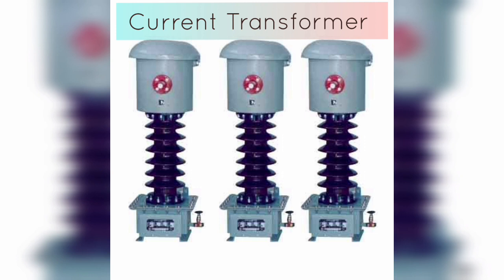An electrical current transformer (CT) is a type of instrument transformer used to measure high levels of electrical current in power systems. CTs work on the principle of electromagnetic induction, where a changing magnetic field induces a voltage in a conductor. The primary winding of a CT is connected in series with the conductor carrying the high current to be measured. The secondary winding is connected to a measuring instrument such as a meter or relay, and provides a reduced current output proportional to the original current. The ratio of primary to secondary windings determines the amount of current reduction.